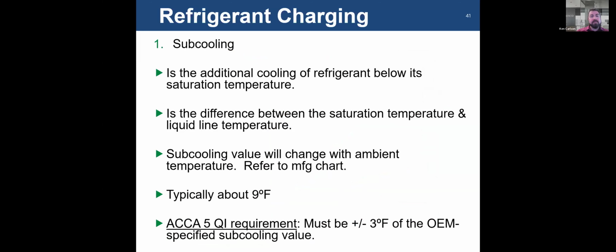Conversely, subcooling, right? So what is subcooling? It's the additional cooling of refrigerant below its saturation temperature. We show that pressure temperature relationship chart. At a given pressure, it has a saturation temperature. If you are below that temperature, you are in a liquid state. If you're above that temperature, you're in a vapor state. Again, it's the difference between the saturation temperature and the liquid line temperature.